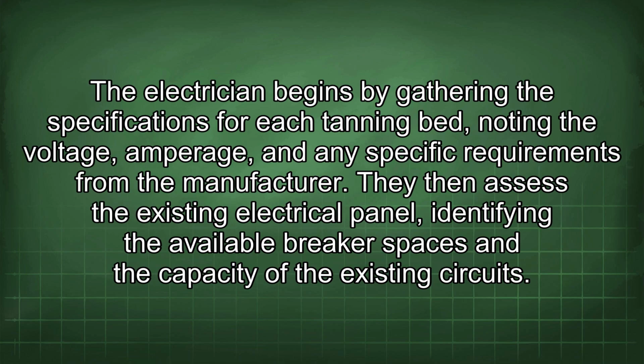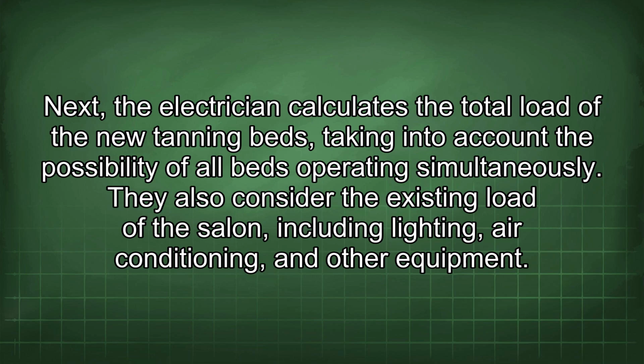The electrician begins by gathering the specifications for each tanning bed, noting the voltage, amperage, and any specific requirements from the manufacturer. They then assess the existing electrical panel, identifying the available breaker spaces and the capacity of the existing circuits. Next, the electrician calculates the total load of the new tanning beds, taking into account the possibility of all beds operating simultaneously. They also consider the existing load of the salon, including lighting, air conditioning, and other equipment.